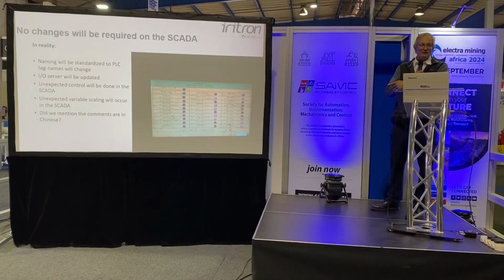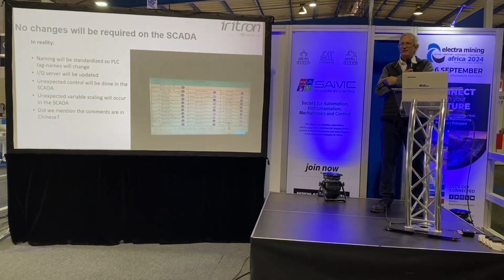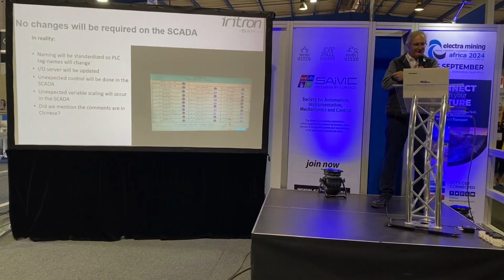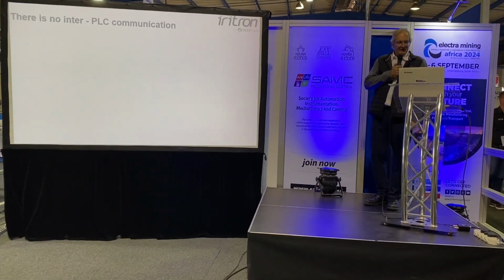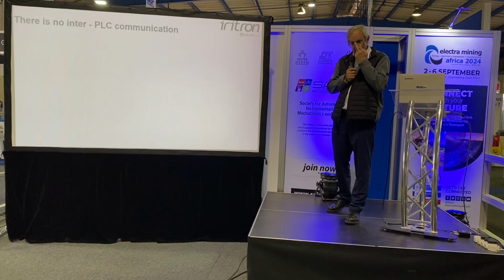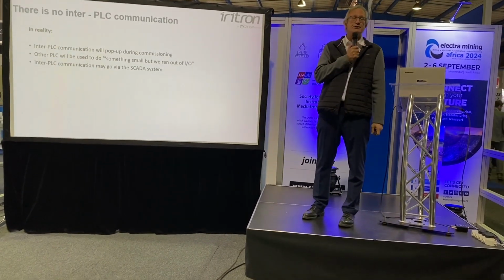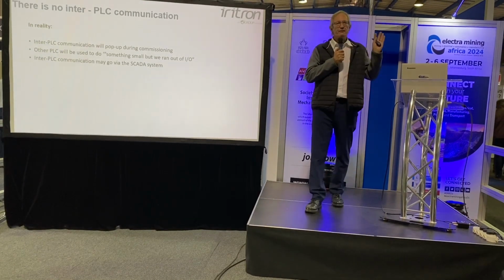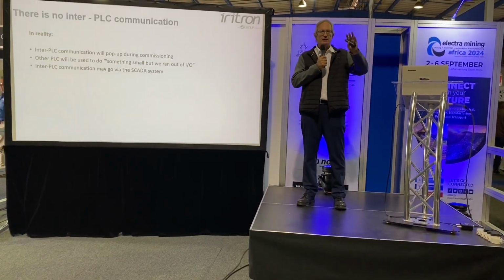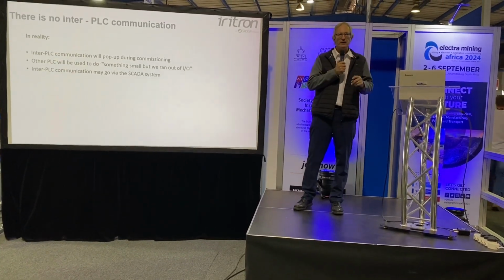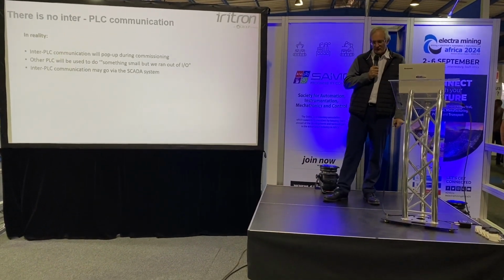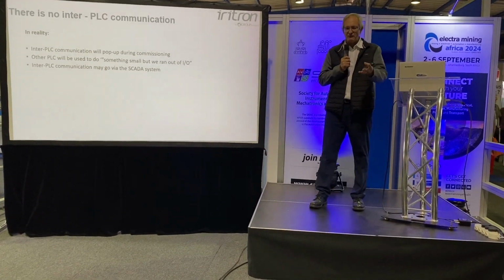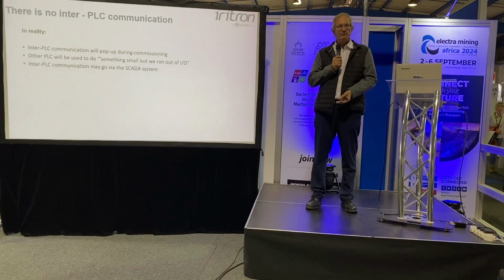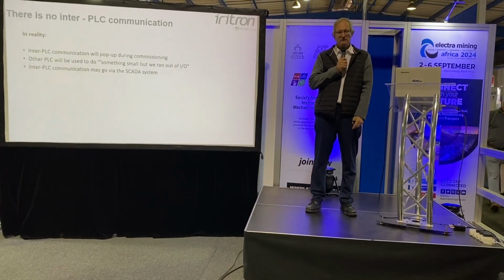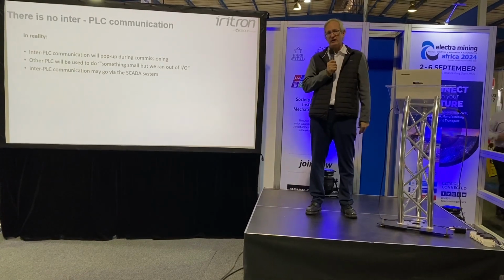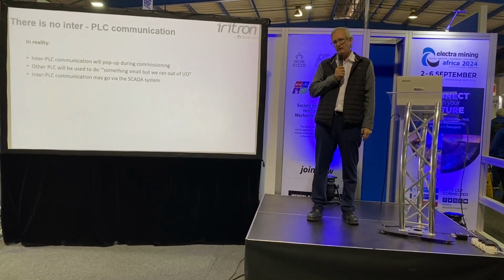And did we mention that some of the comments in the PLC are in Chinese? Or all the comments in the PLC are in Chinese? This is another one that has bitten us a few times. No inter-PLC communication. We don't have inter-PLC communication. All communication goes from the PLC into SCADA. There's nothing until you get to site and you start commissioning and you find that something's not working. So we're creating the recipe and we're sending it through to the SCADA, or we're creating the recipe in the SCADA and we're reading it with the PLC, but nothing happens.